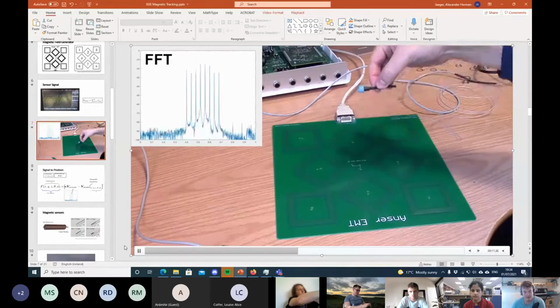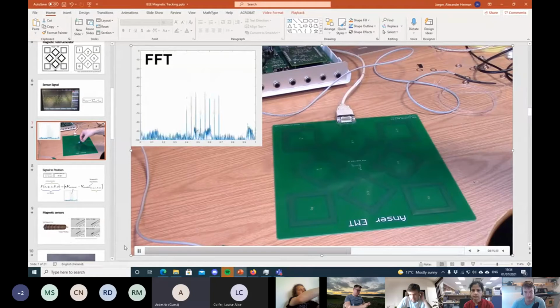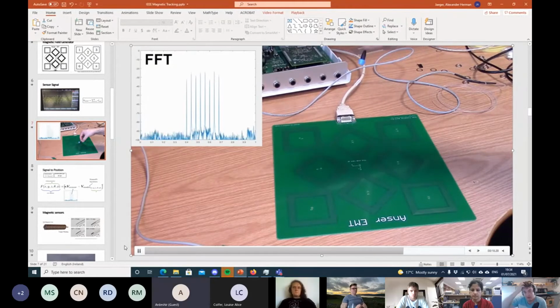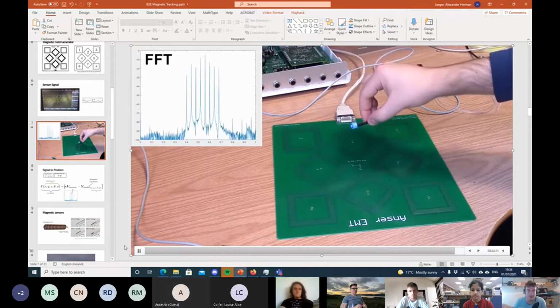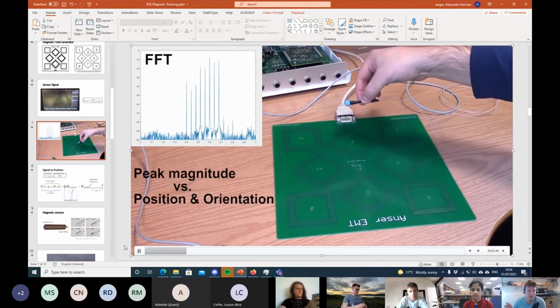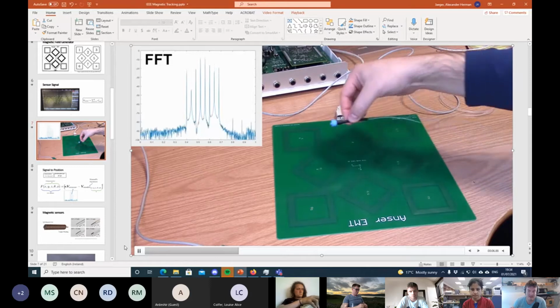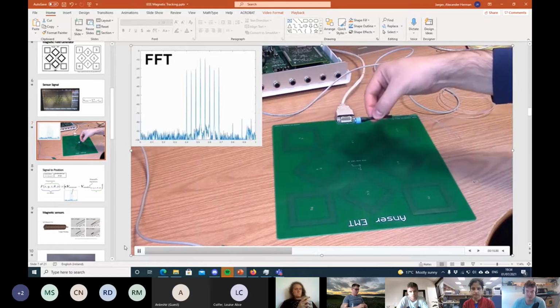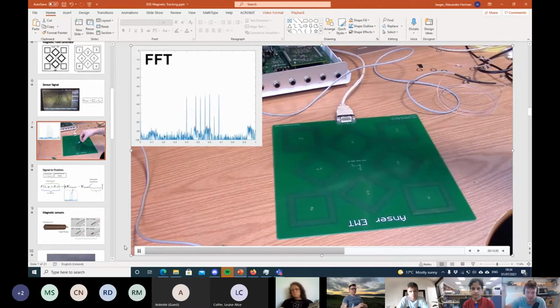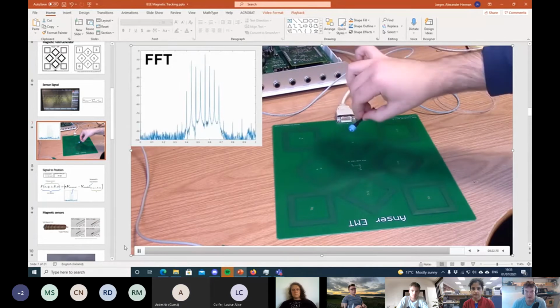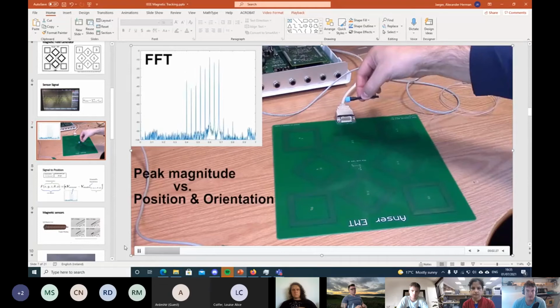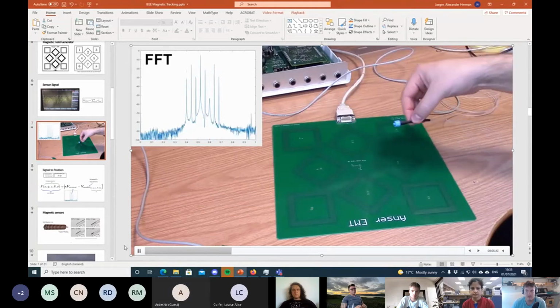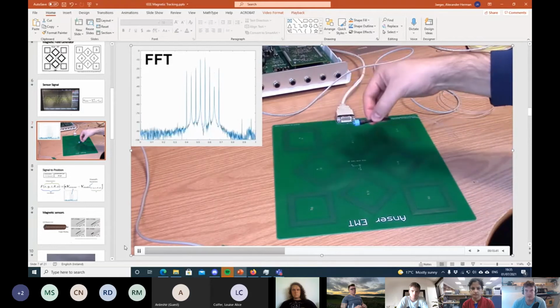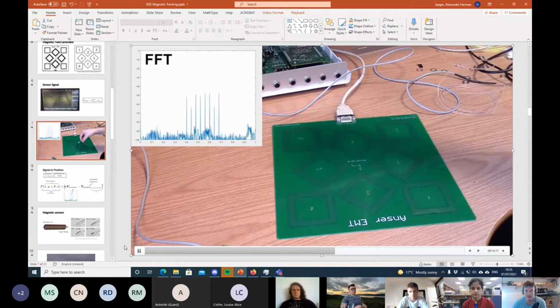To address the first part, the minimum resolution or minimum movement that can be detected is extremely small. Of course, it depends on what height you're at above the field generator. In the pose I'm at in this video, I'm about 5 or 6 centimeters up. Now I go up to 30, but initially when I was going side to side, I was about 6 or 7 centimeters above the surface. There you can get to hundreds of microns level of precision. From when I did the experiments, I would estimate about 300 to 400 micron of resolution.